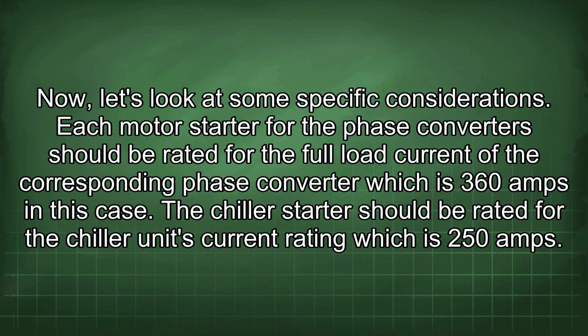Now let's look at some specific considerations. Each motor starter for the phase converter should be rated for the full load current of the corresponding phase converter, which is 360 amps in this case. The chiller starter should be rated for the chiller unit's current rating, which is 250 amps.